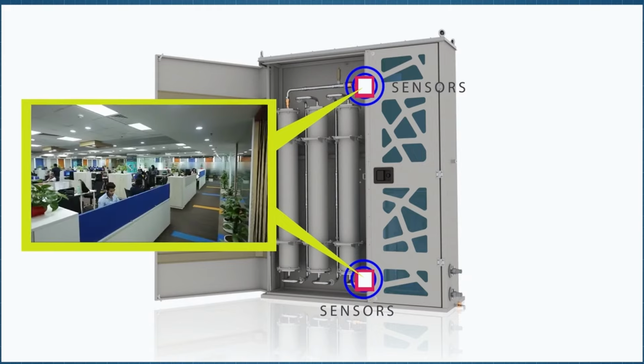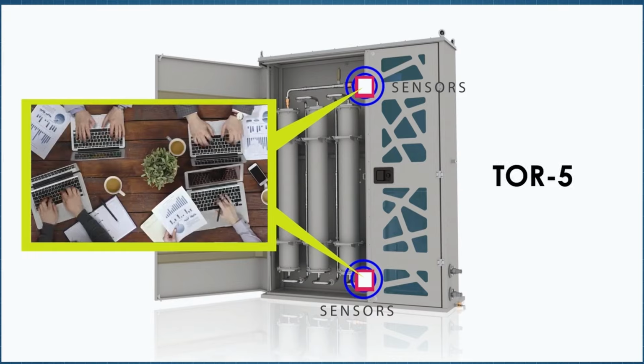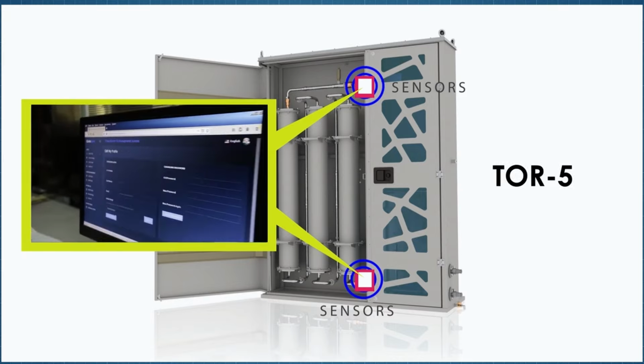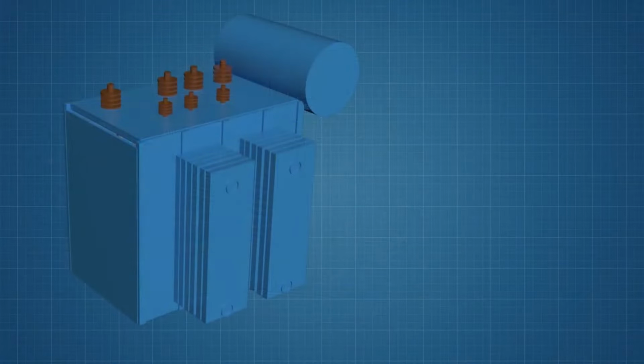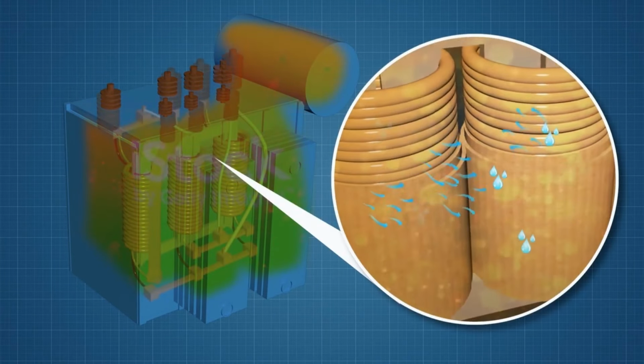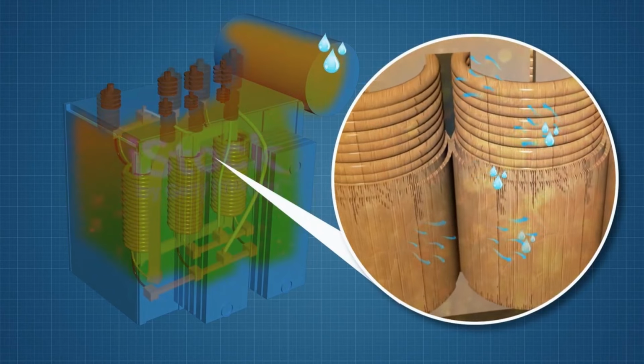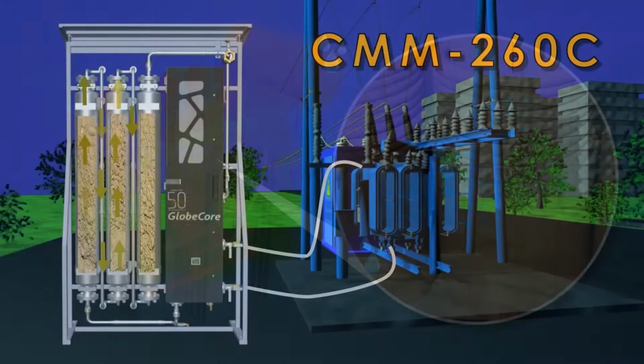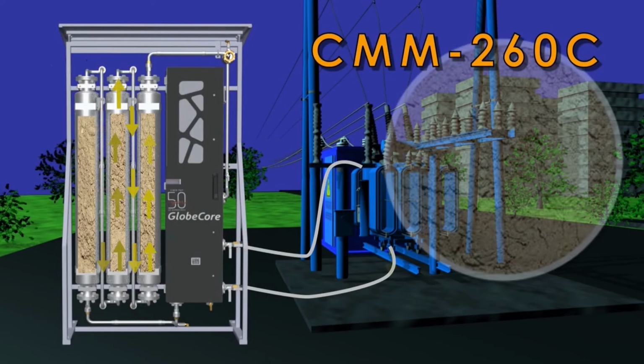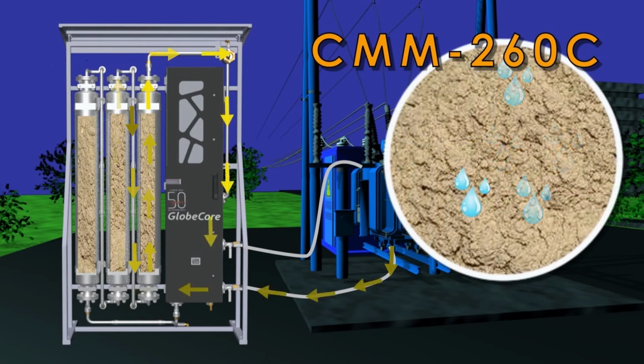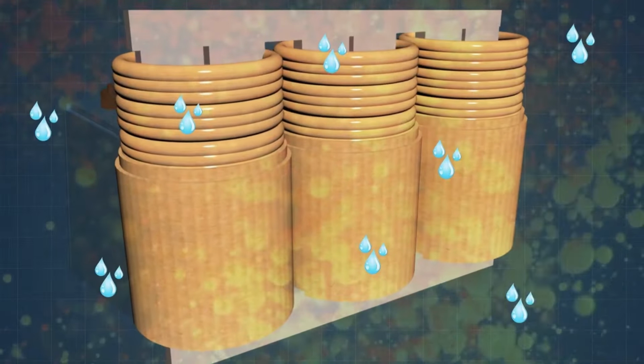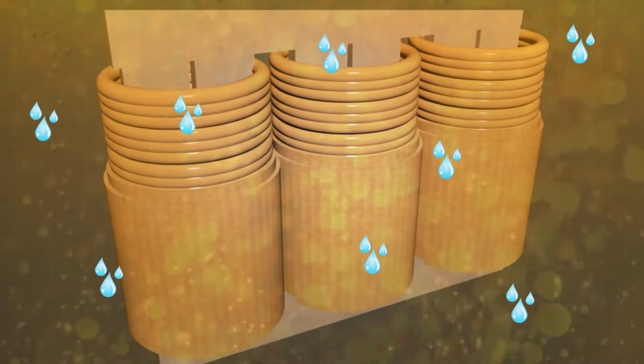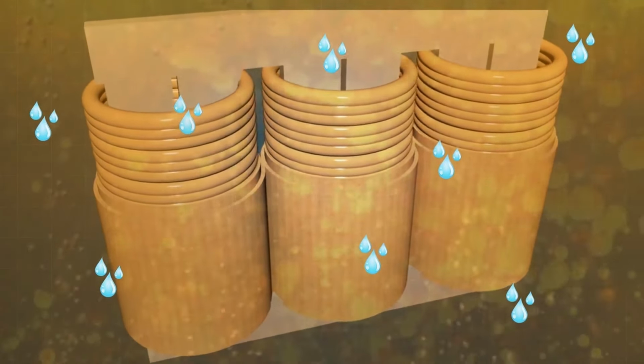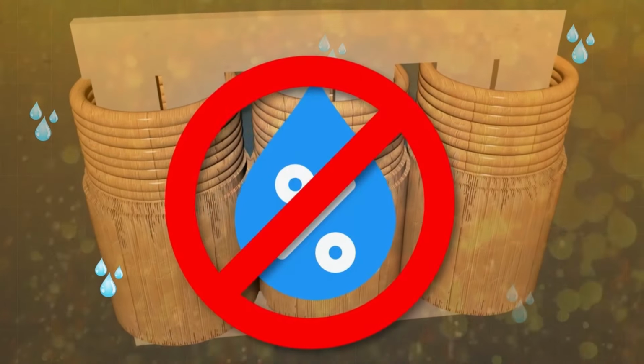Let us take a closer look at the drying process. As load and temperature of the transformer fluctuate, water is in constant motion between the solid insulation and the oil. Using the continuous GlobeCore drying, we feed dry oil into the transformer, which takes water from the solid insulation, carries it out, and returns to the transformer dry. The process removes water not only from the oil, but also from the solid insulation. Therefore, this GlobeCore process facilitates keeping the water content in the solid insulation at a safe level, preventing cellulose breakdown.